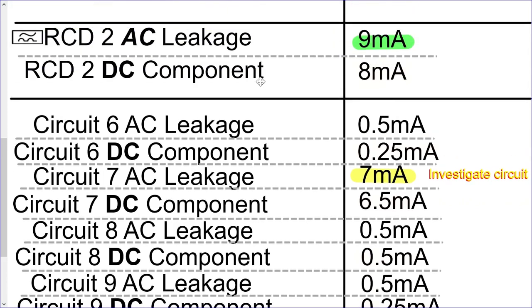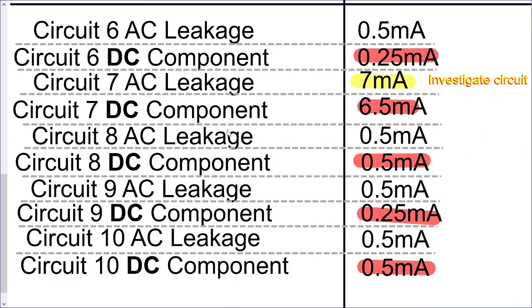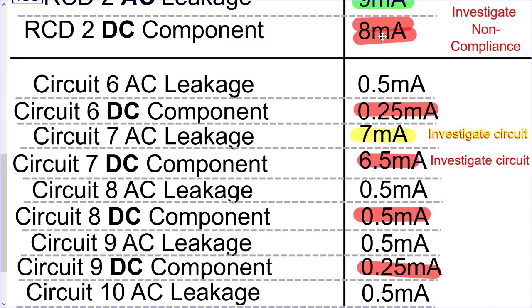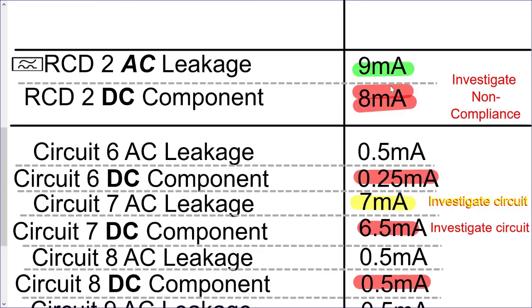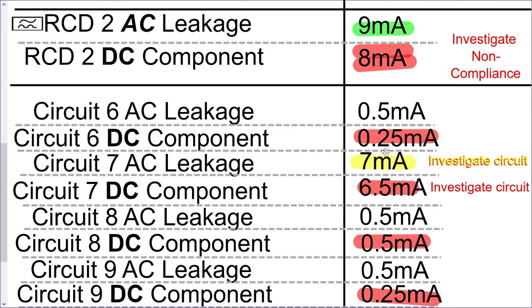All right. But looking at the DC components through that second RCD, you'll see there we've got 8 milliamps. Now remember, the maximum leakage that we can have for this type A RCD is 6 milliamps, so we have to investigate this non-compliance. So we're then having a look at all of the DC components going back through each one of those RCDs, and sure enough, that circuit number 7 that we're already investigating anyway, what have we identified? We've identified that we've got 6.5 milliamps here. So hopefully once we identify what's going on here, with the higher leakage, and if we further subdivide the installation, through that investigation, we'll hopefully bring that 8 milliamps down below the 6 milliamps, ensuring that when the RCD operates, it's going to operate within the time frame required.